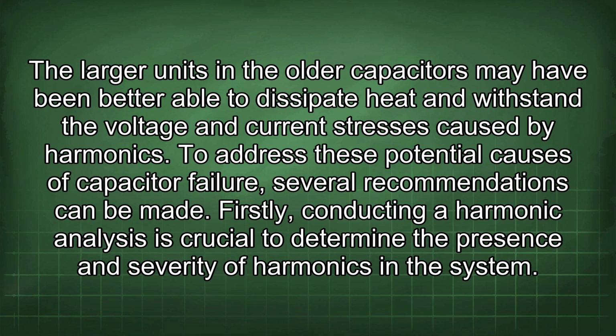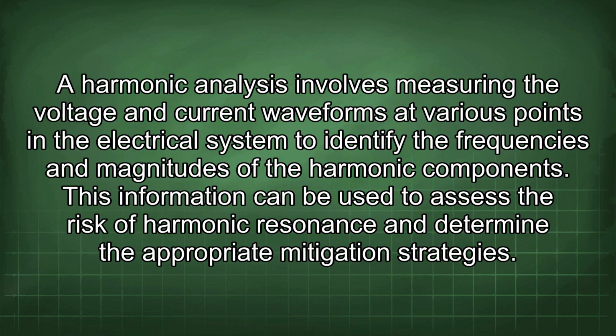Firstly, conducting a harmonic analysis is crucial to determine the presence and severity of harmonics in the system. A harmonic analysis involves measuring the voltage and current waveforms at various points in the electrical system to identify the frequencies and magnitudes of the harmonic components. This information can be used to assess the risk of harmonic resonance and determine the appropriate mitigation strategies.